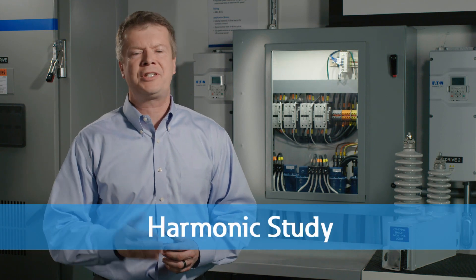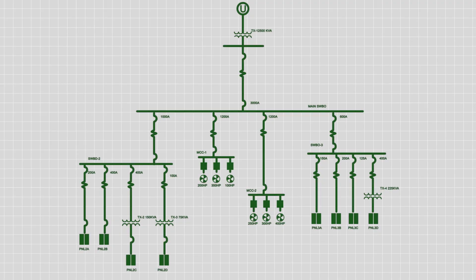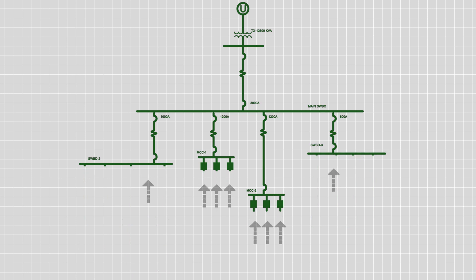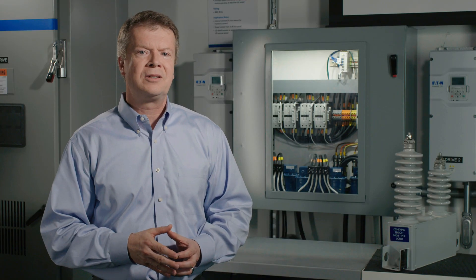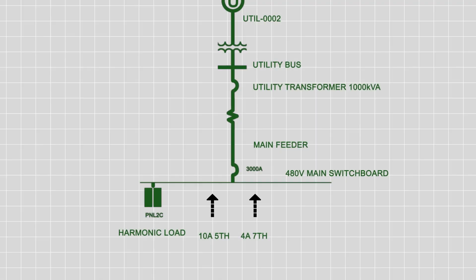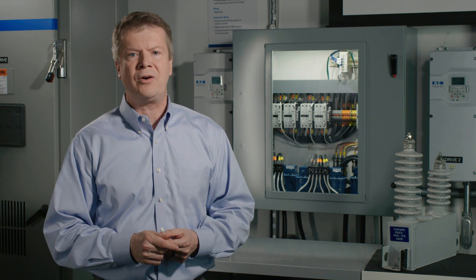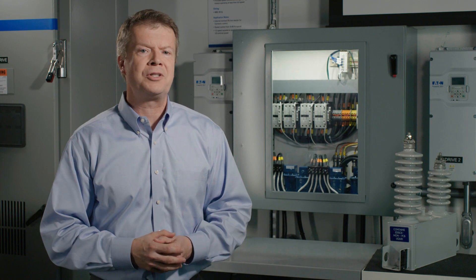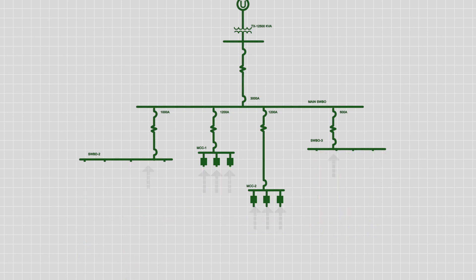A harmonic study is a computer simulation of a power system to evaluate voltage and current distortion at various points in the system. It is very similar to a load flow study, but it begins with the known sources being replaced with constant current sources of harmonics. These harmonic sources are placed at each load location or at various other injection points throughout the system — say 10 amps of 5th harmonic and 4 amps of 7th harmonic added to a particular bus. A standard load flow study uses one source of voltage and power, typically the utility or a generator or a couple of power sources in parallel. Likewise, a harmonic study first uses the same standard load flow analysis to determine the base case 60 Hz load flow and then superimposes single or multiple harmonic current injection sources at specific points throughout the system.